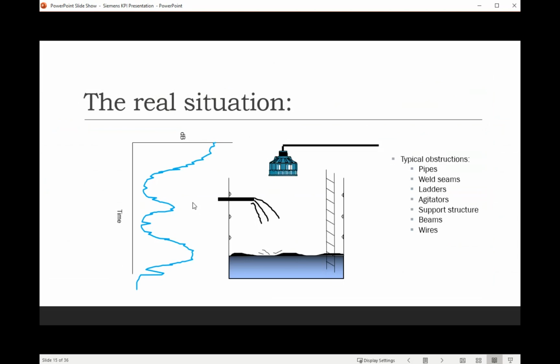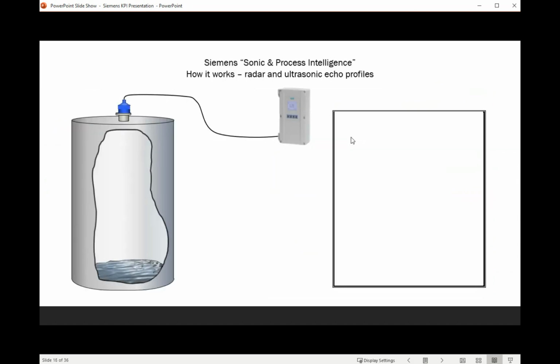ultrasonic. With this echo profile, you can see as the sensor sends a signal down, we've got a little bit of an echo off of our fill pipe, and then a larger echo off of our water. So it's always important to take into consideration the mounting of your transducer when using an ultrasonic transducer in this kind of application. If you don't have the ability to move these or to mount the transducer in a certain area, we do have ways to work around it using our sonic intelligence and auto false echo suppression, those kinds of things. So I'm going to turn it back over to Mark, and he's going to talk a little bit more about our sonic intelligence.